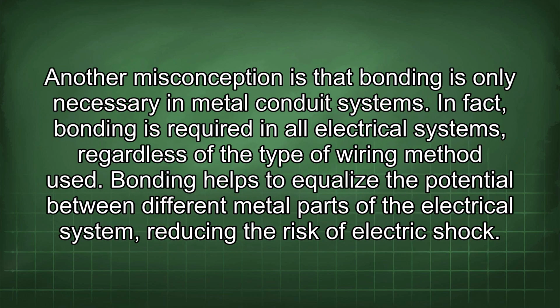Another misconception is that bonding is only necessary in metal conduit systems. In fact, bonding is required in all electrical systems, regardless of the type of wiring method used. Bonding helps to equalize the potential between different metal parts of the electrical system, reducing the risk of electric shock.